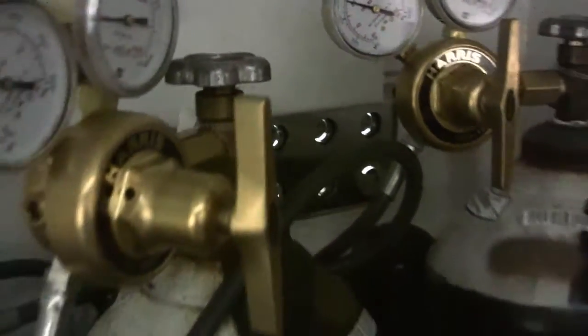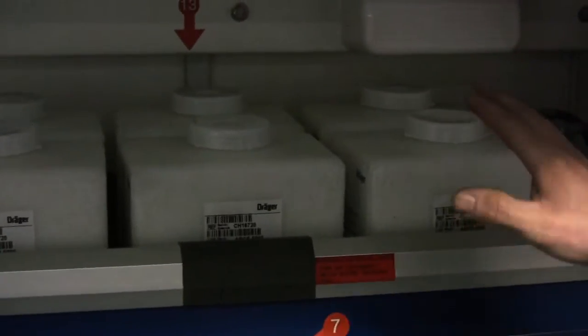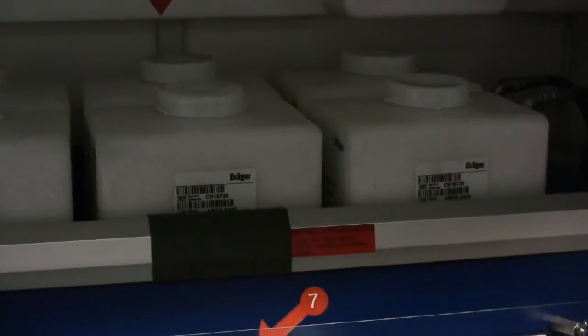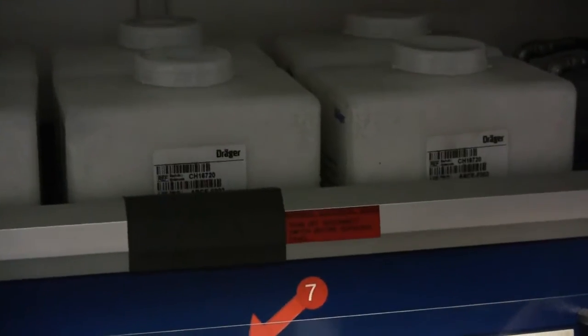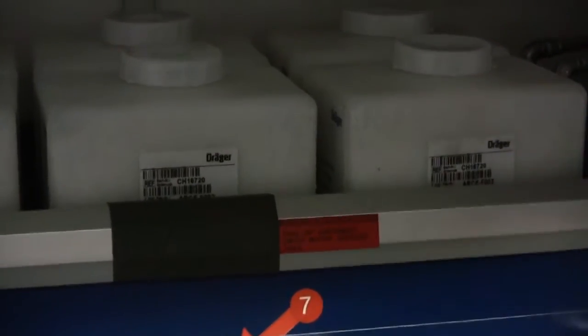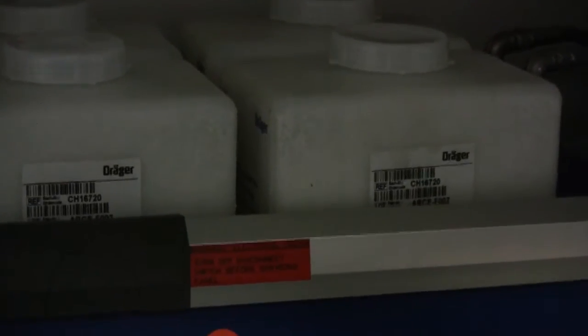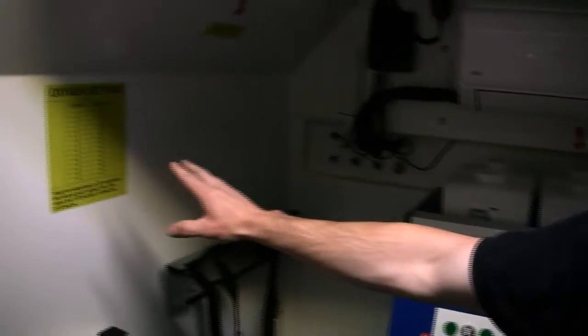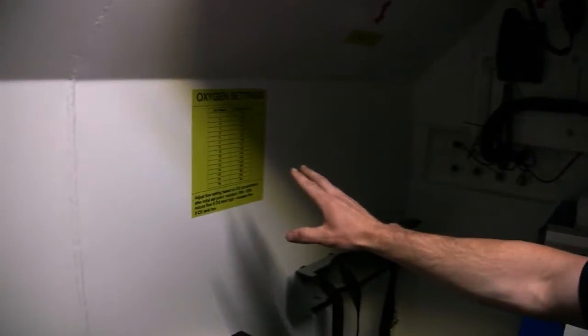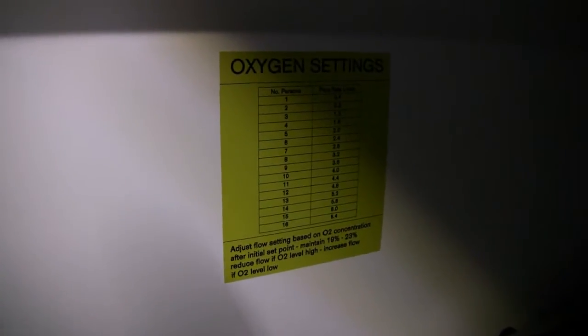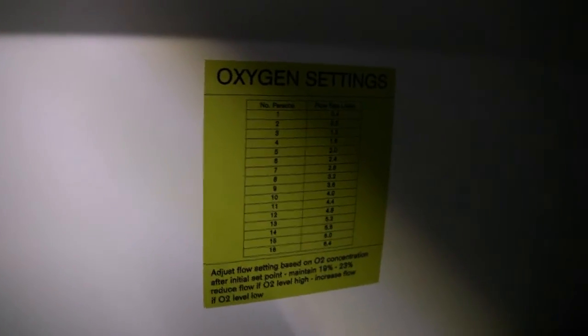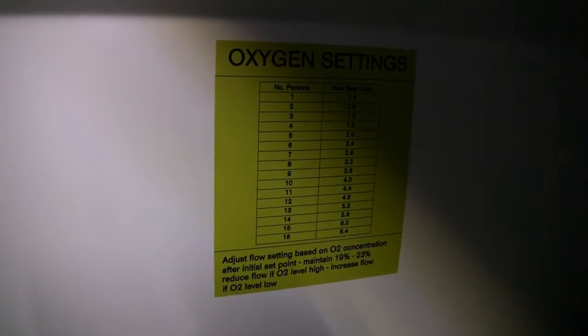And that's relieving 100%. If you lose your mine air, you're using our soda lime scrubbing. That's what this is. So it's not both. It's one or the other. You have mine air, you turn it on, you sit down, you're good. Turn on the air conditioning, you're okay. If you don't have air, then this is soda lime scrubbing. We have oxygen cylinders which aren't here at the moment. We have oxygen cylinders replenish the oxygen that we consume. And the CO2 that we generate is absorbed through the soda lime system here.